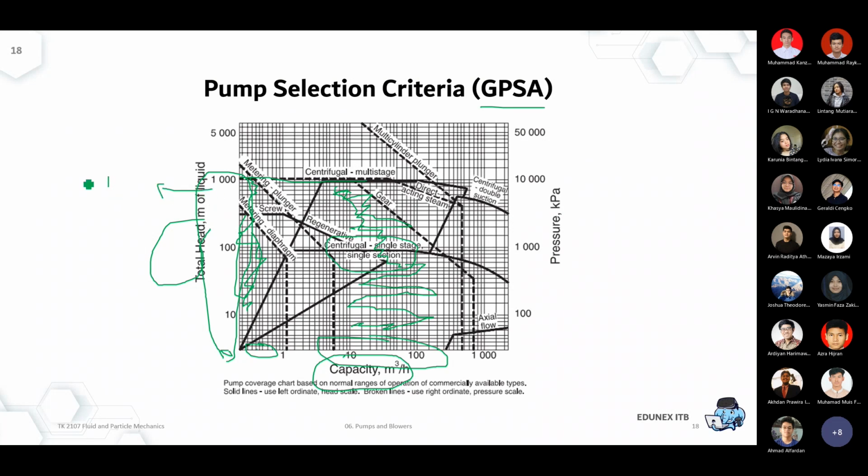That should explain why we chemical engineers love pumps very much compared to compressors. It's able to compress water from 1 bar to 100 bar using one stage. From 1 to 100, it can be done using a single stage centrifugal. Usually that's doable and usually that's the most efficient one.